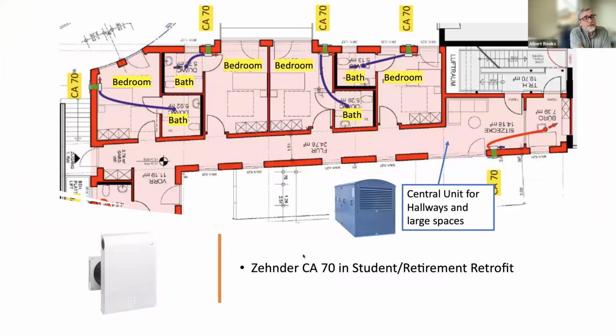Here's another building, kind of a classic student, single occupant, retirement type building. And so, same CA70. In this case, extreme left, one in a bedroom, and it just supplies that bedroom, and then maybe a little bit of ducting over to that bathroom. Or you could just depend on the undercut of the door in the bath to pull some moisture out. It works a little better on the supply side, but if you can run some ducting over into that bath, then you've got a surefire way to get constant exhaust flows and constant supply flows in that bedroom. And that would go from maybe a not so great situation to something that's really pretty nice. Once you introduce good ventilation in a building, you can feel it immediately. It's a really strong effect.